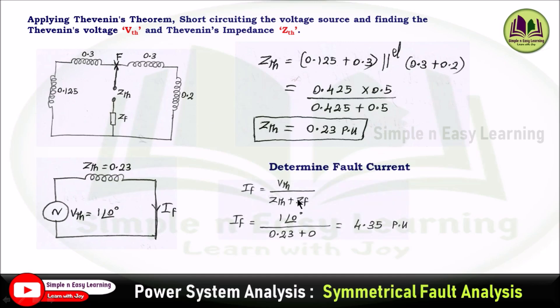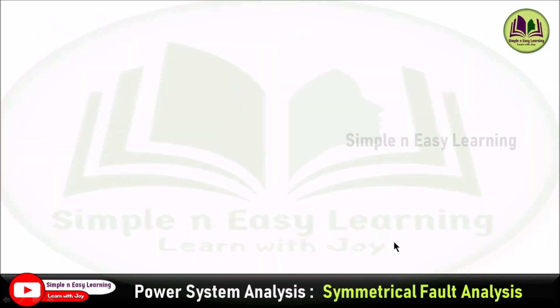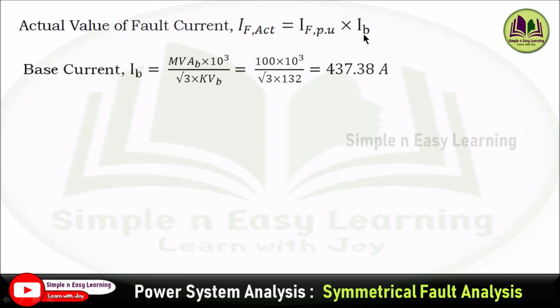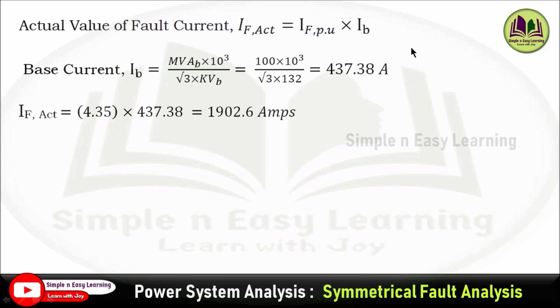The fault current is I_F = V_Thevenin / (Z_Thevenin + Z_F). Since the fault impedance is not specified, Z_F = 0. So I_F = 1∠0° / 0.23 = 4.35 per unit. The actual fault current equals the per unit value multiplied by the base current, where base current = (MVA_base × 10³) / (√3 × kV_base). With 100 MVA base and 132 kV at the fault location, base current = 437.38 A, giving an actual fault current of 1902.6 A.